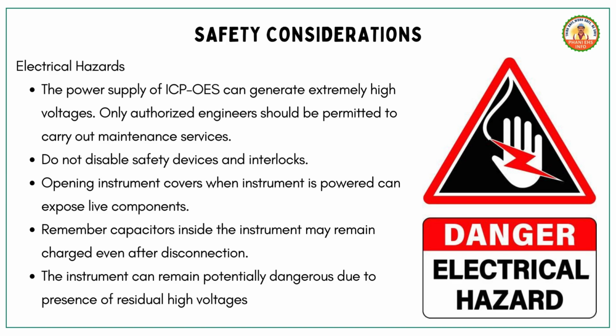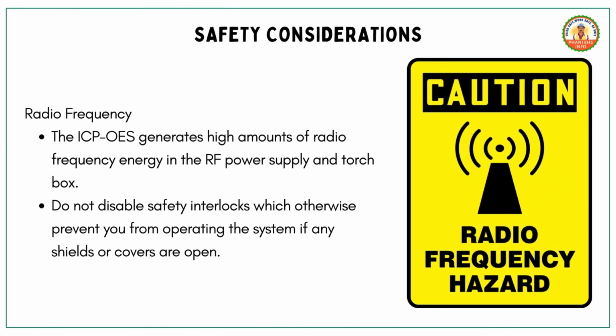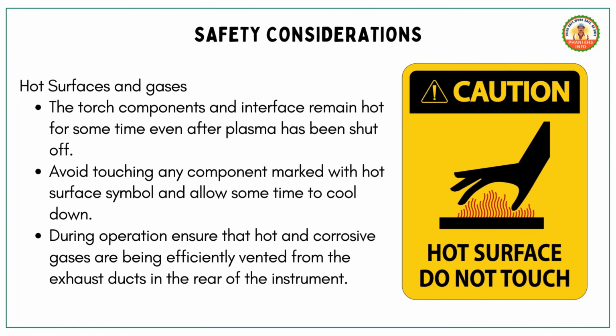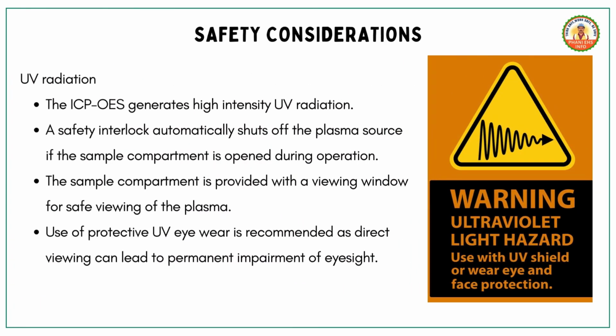Safety considerations. Electrical hazards. High voltages require authorized engineers for maintenance. Safety devices and interlocks must not be disabled. Opening instrument covers with power on exposes live components. Capacitors may remain charged even after disconnection. Radio frequency. High amounts of RF energy are generated and should not be tampered with. Safety interlocks prevent operation if shields or covers are open.